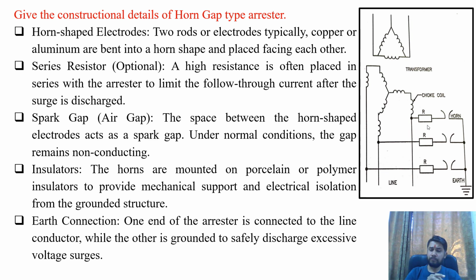Spark gap. The space between the horn-shaped electrodes acts as a spark gap. Under normal conditions, the gap remains non-conducting. So the medium between these two is air, so no need to specify the material used for it. Insulators. The horns are mounted on porcelain or polymer type high strength insulators to provide mechanical support and electrical isolation between the live part and ground part. So it is an electrical isolation.